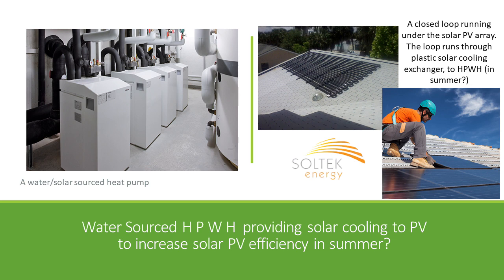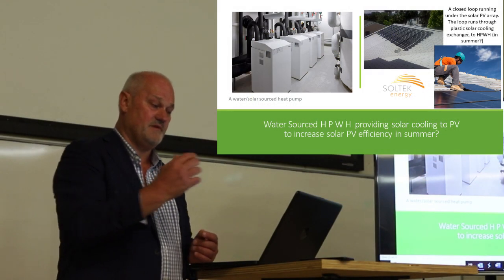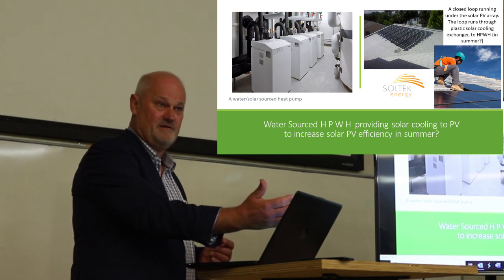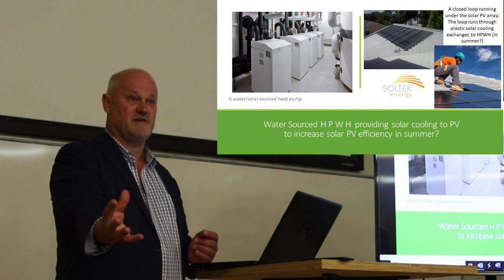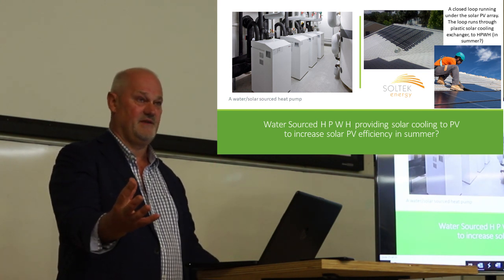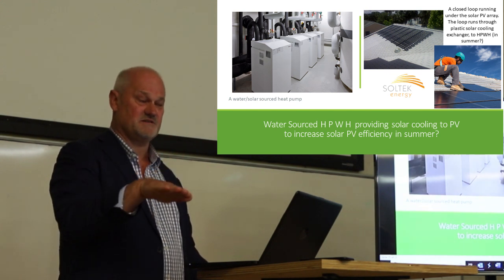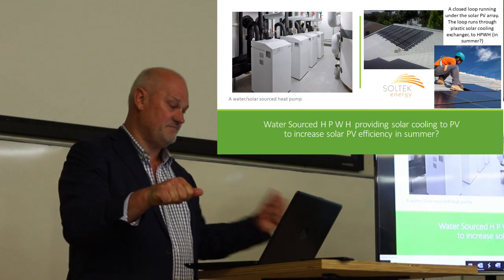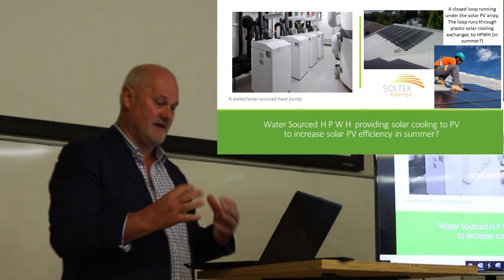Why not use a water source heat pump and something like traditional solar pool heating plastic tube? Okay? So the way it would work is that you'd have a closed loop going from the heat pump up to the heat exchanger and back. And that solar collector on the roof there is actually getting cold because it's effectively an evaporator for the heat pump. So the heat pump has a cold side, just like you would do with a refrigerator, and you've got a hot side. So absorbing heat and the surface gets cold, expending heat and the surface gets hot. That's effectively how a heat pump works.